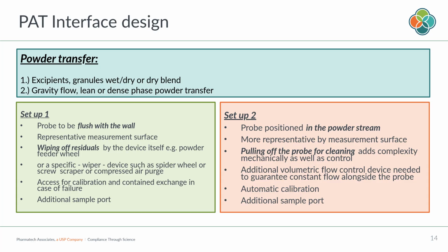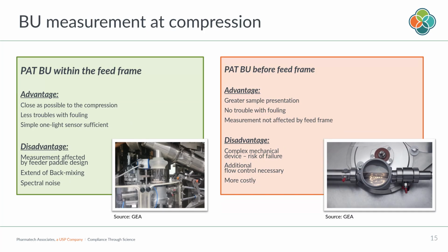Otherwise you have a more complex system, as you can see here—a nice example from blend uniformity measurement applications. You can do this within the feed frame; it's a bit hard to see in this picture, but there's a sensor going straight down into the feed frame. Or in cross section you have a device like this one from GEA, the Lighthouse Probe, with multiple light sources crossing the diameter of the housing where the material comes in, so you can measure it.